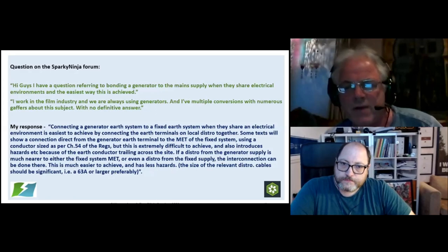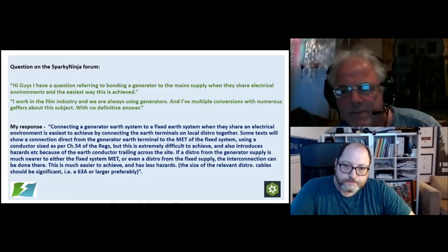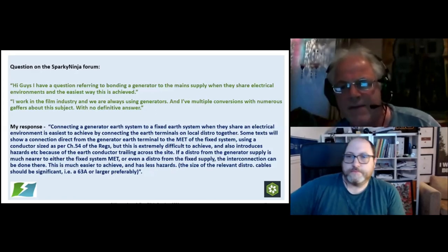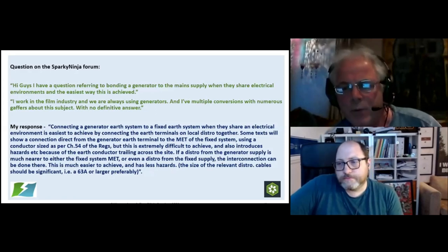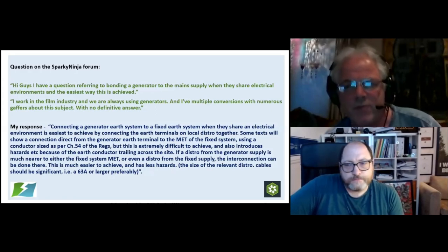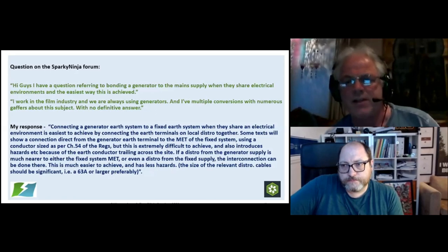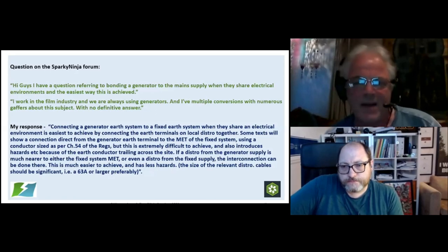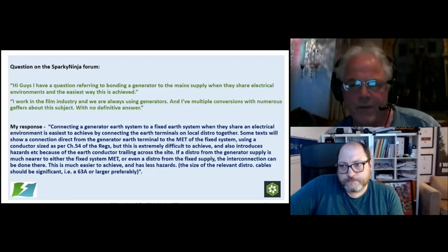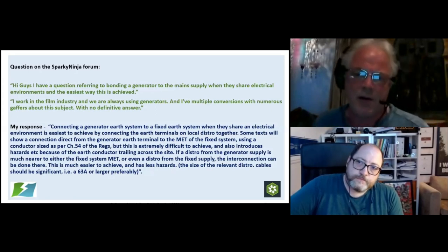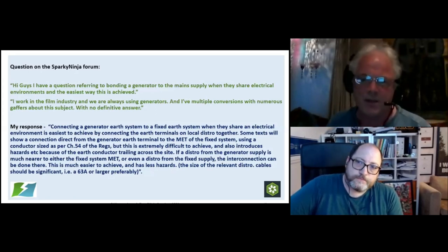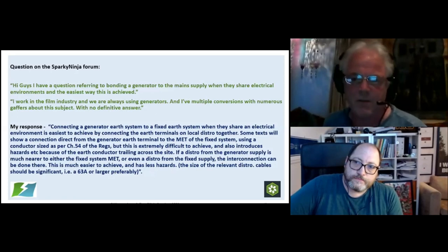Now the generator earth electrode, as we said before, the generator has its own earth anyway, and even if it was floating in midair, it would still have effectively an earth. But we tend to put an earth electrode in for a reference, in other words, referencing the generator to true earth. But that may be quite a distance away from the building, so you may get a difference in voltage between the two earthing systems. Okay, and to overcome that, 7909 recommends the connection of the two earthing systems within the building.